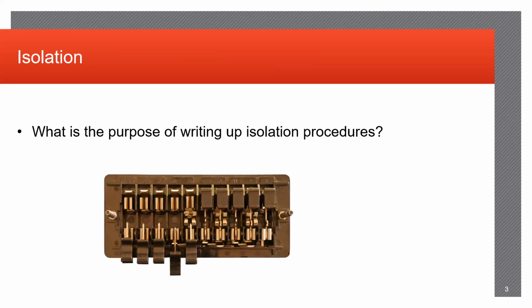So just a quick overview, going over some of the stuff we left off with last Thursday. Just very quickly going over the isolation procedures for prepping testing relays specifically. Quick purpose for writing up isolation procedures. They specifically are used to avoid misops, damage to equipment, or risk of injuries to personnel. Removes in-service sections of station, avoiding any form of DC or AC power flow through pieces of equipment that may be placed into or out of service.